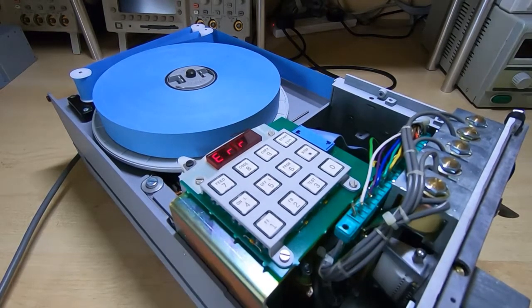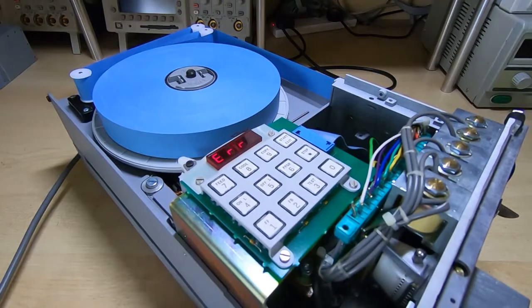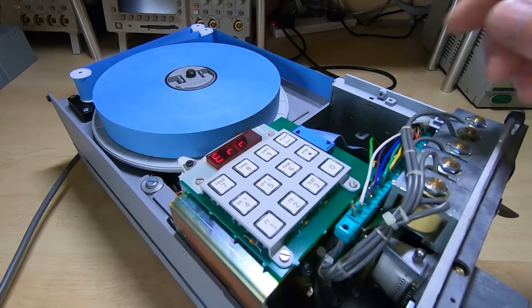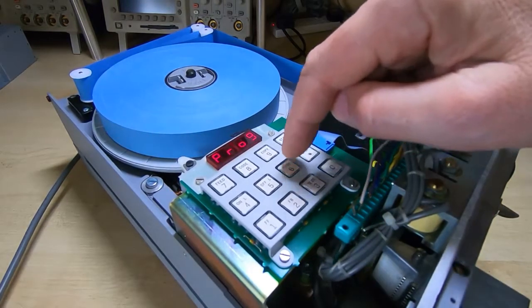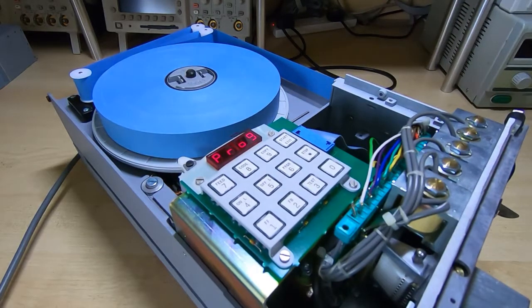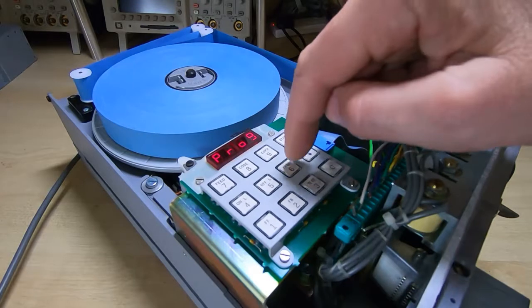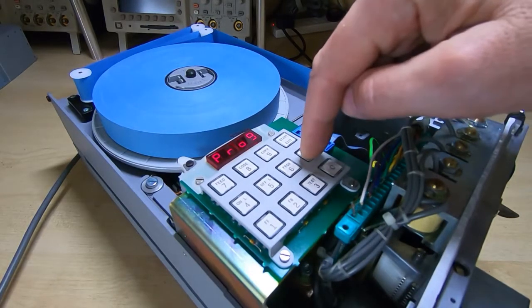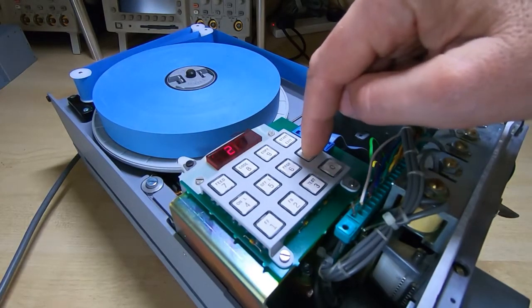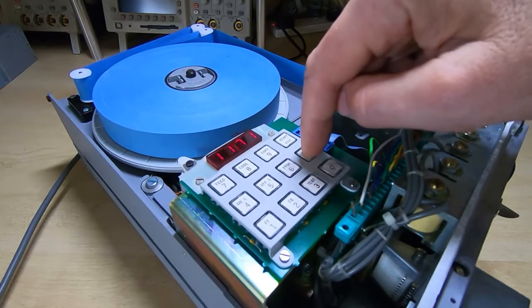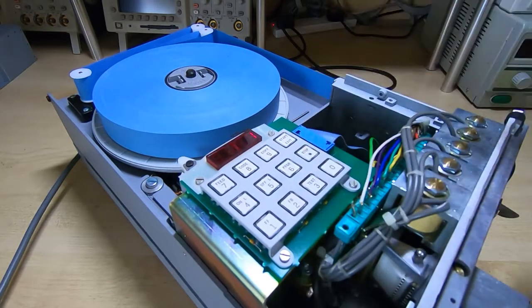So again, I don't know if you can see this, but it's come up with an error. If I exit the error, I can now go into normal operation of the machine - in other words, we've bypassed the passcode. Everything works the way you'd expect, including being able to go through all the system settings, parameters, etc. So I've gone through and changed those to what I need them to be. That problem's solved.